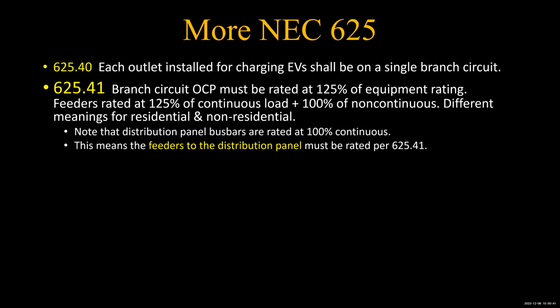You've got a 200 amp bus bar, and if you've got a 200 amp feeder, which would be 3/0 copper, then you can have that 150 amp breaker and you can bump it up to 175, and then you're okay. You don't have to do a service change. You just change out the main breaker. So you have to be very attentive to exactly what's in that box.